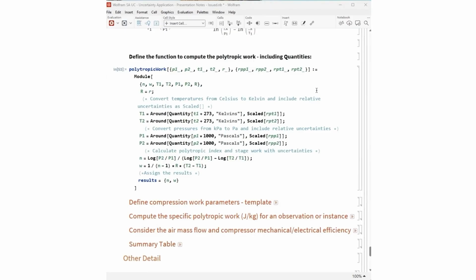Now that the equations have been defined, I've built a polytropic work function. It takes the measured air operating parameters: inlet pressure, inlet temperature, outlet temperature, the gas constant, and the measurement uncertainties in these values.